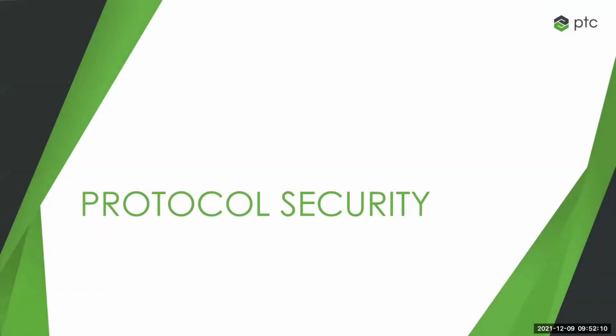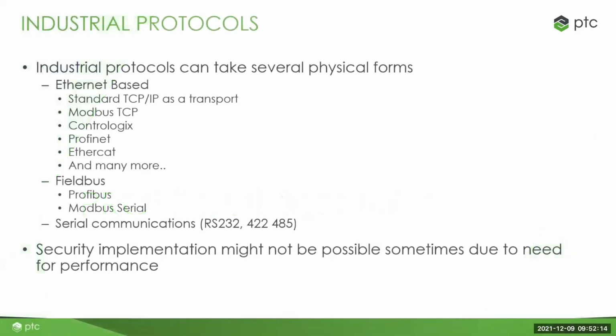So moving on to the next section, we talk about protocol. A lot of industrial protocols can take several forms. It could be standard TCP/IP, which is an Ethernet-based driver, or it could be a fieldbus, a specific fieldbus such as Profibus. It could be serial RS-232, 422, 485, standard stuff. Sometimes security implementation might not be possible because of the need for performance. In that kind of situation, what you want to do is try your best. Try to have as much network segmentation as you can, or even deploy an IDS to monitor the flow. Because to be honest, our OT traffic is quite specific, very consistent in terms of the flows.